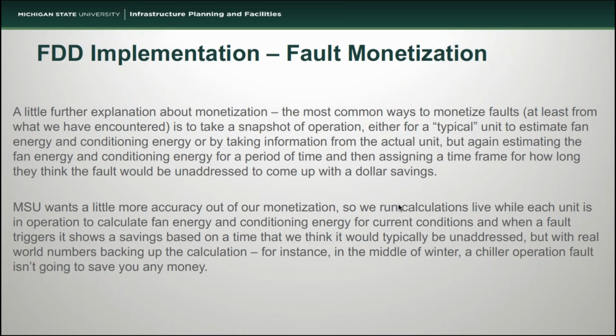And it's something that MSU fundamentally disagrees with, because if we have a chiller fault in the middle of winter when it's 5 degrees out, that chiller fault is not going to save us any money because that chiller is not in operation. So for our monetization, we run calculations using the fan affinity laws and the pump affinity laws, as well as some BTU calculations, so that when a fault triggers, we are still estimating how long we think a fault would not be addressed, but we're using data that is current to how the unit is operating today. And so at the very least, if it's in the middle of winter, we're not going to say we're going to save thousands of dollars from a chiller operational fault. Or if it's in the middle of summer, we're not going to have an operational fault for the heating valve not heating properly because we don't need heating for that season.